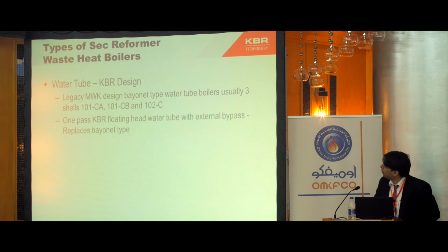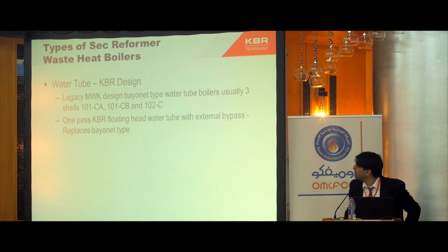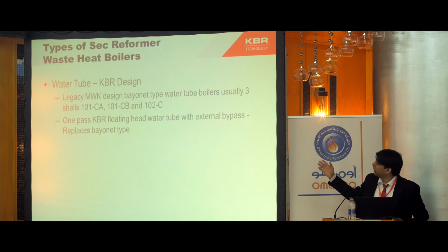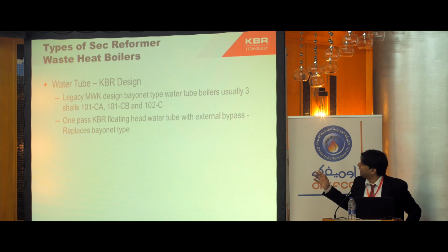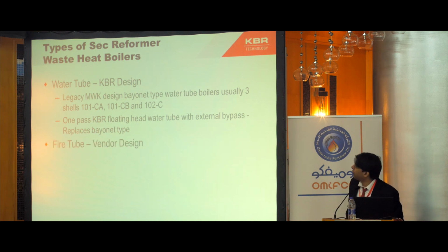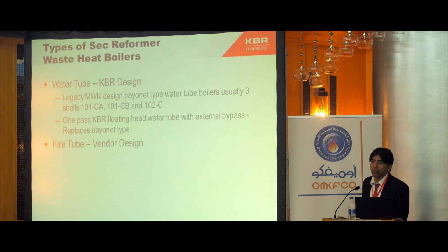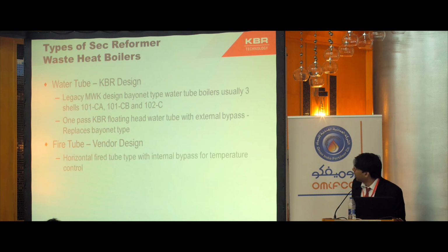The new floating head design, which after 1988 we have provided, has an external bypass. We now only provide this floating head design. And the next one is the fire tube, which is a vendor design, popularly known as the Borsig design. It's a horizontal fired tube type with internal bypass for temperature control.